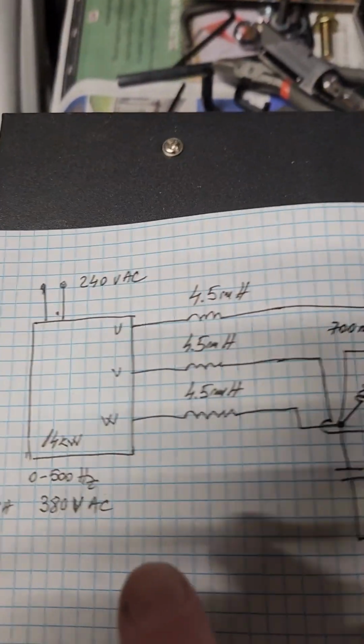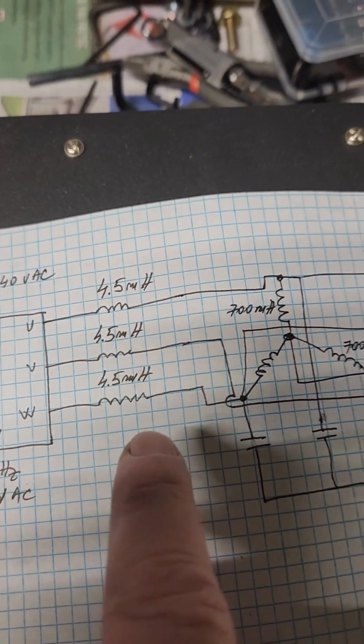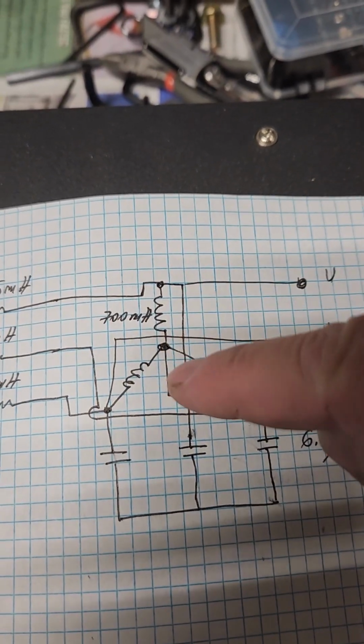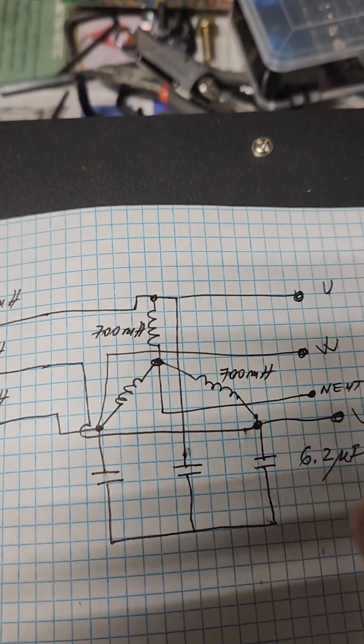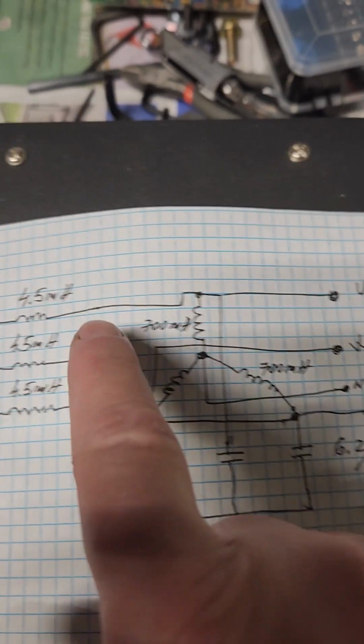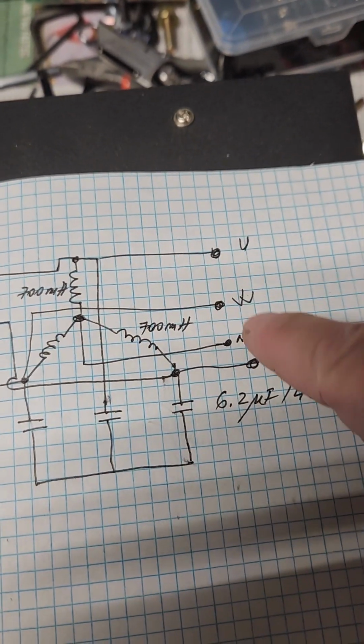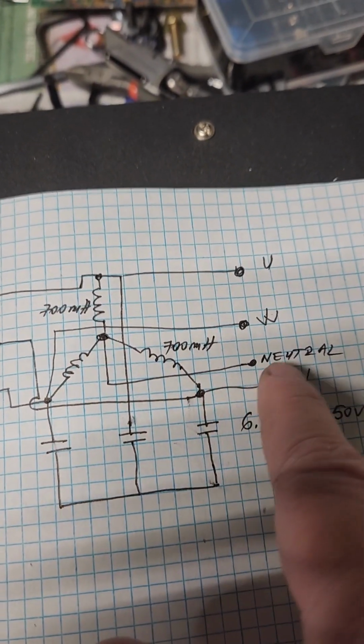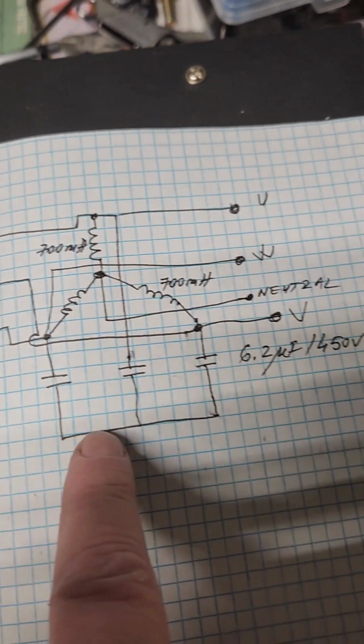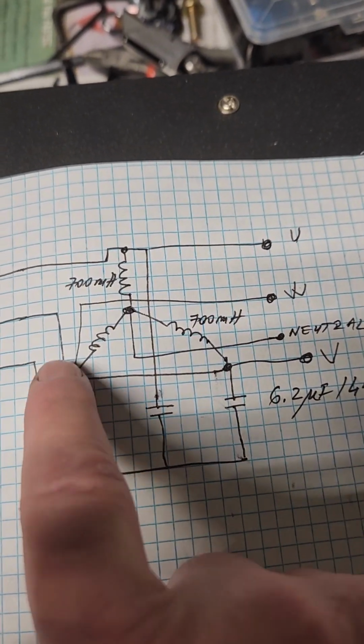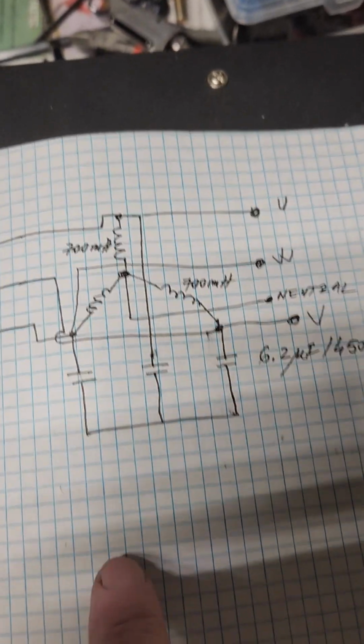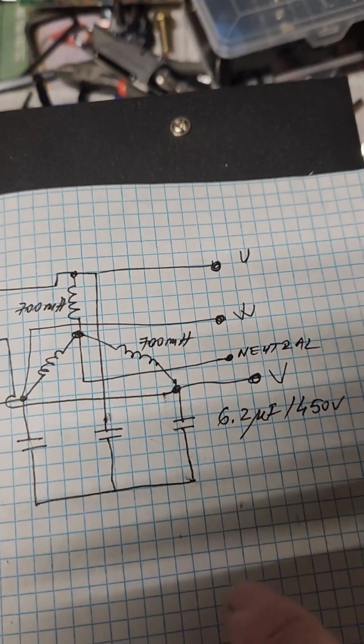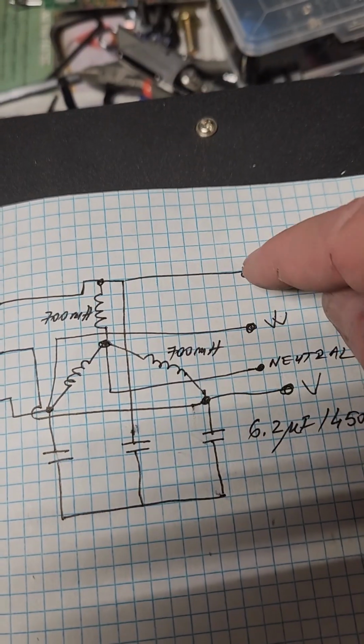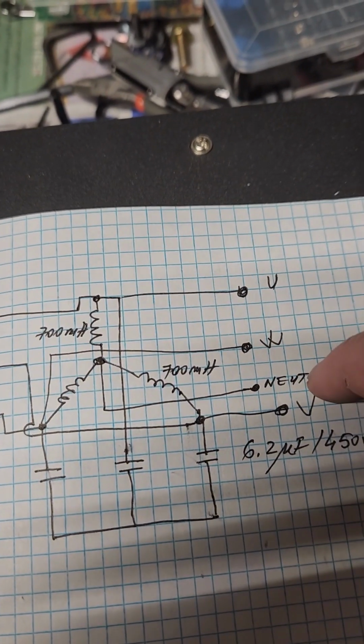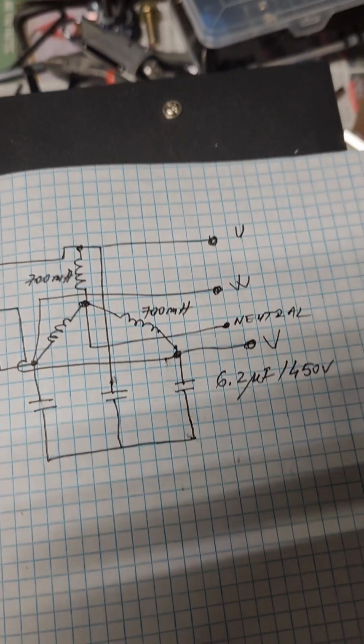So I did a schematic of that, this is how it is. This is an inverter, the three chokes, and there's a star connection here on that transformer, which is not a transformer. All the inputs UVW go directly to the output. This neutral is artificially created, and there are also three capacitors connected together here and nowhere else, not to the ground, nowhere else. So this gives you 380 volts here, and from neutral to any of these three you get 220 volts.